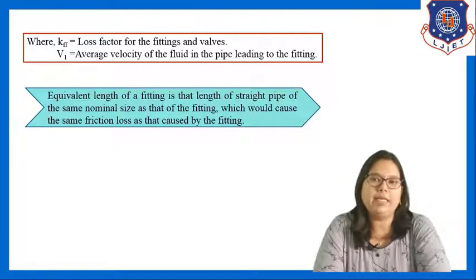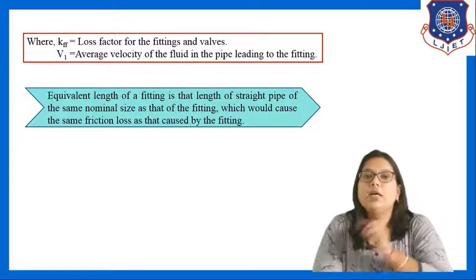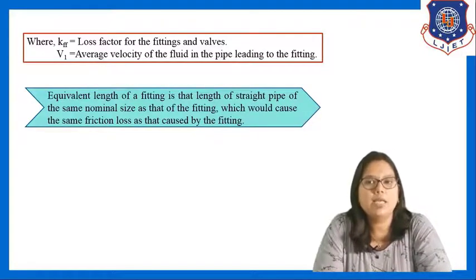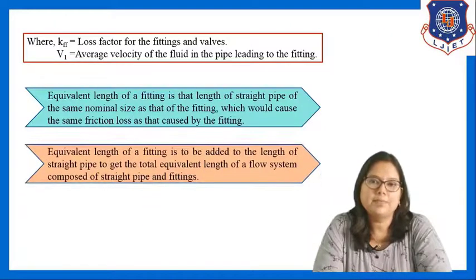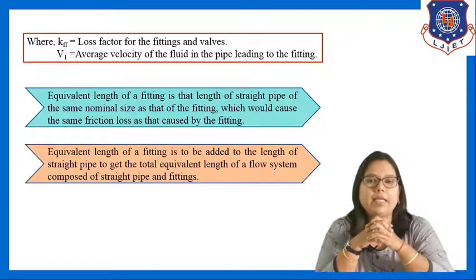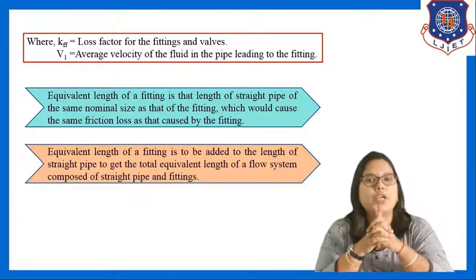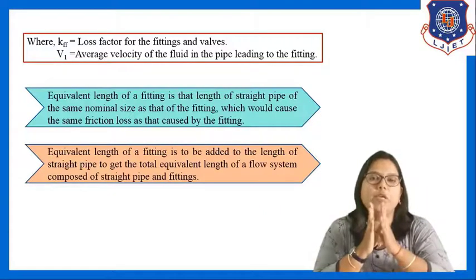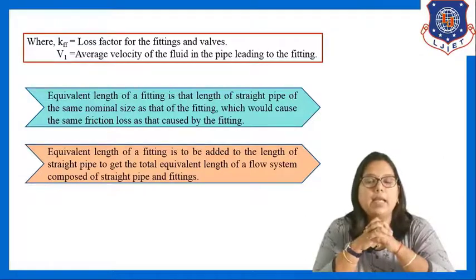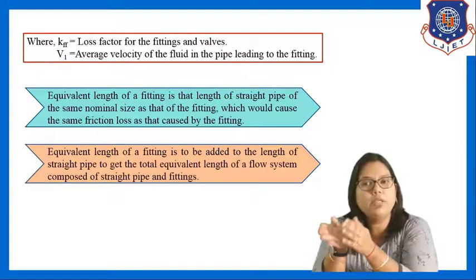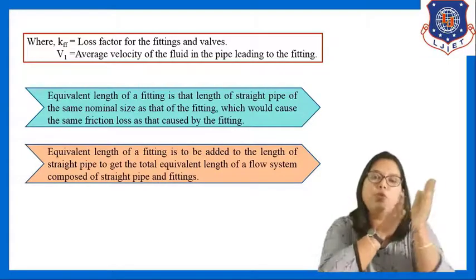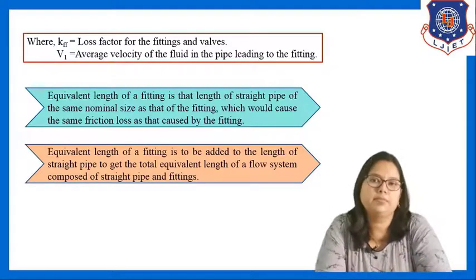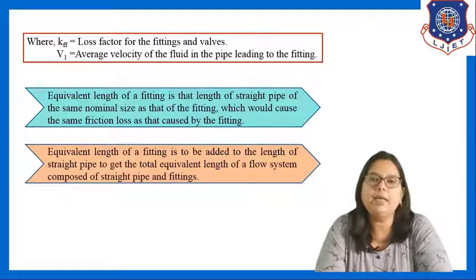The equivalent length of a fitting is that length of straight pipe of the same nominal size as the fitting which would cause the same friction loss as caused by the fitting. The equivalent length of the fitting is to be added to the length of the straight pipe to get the total equivalent length of the flow system.